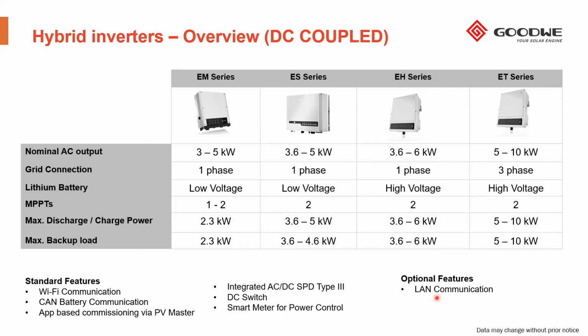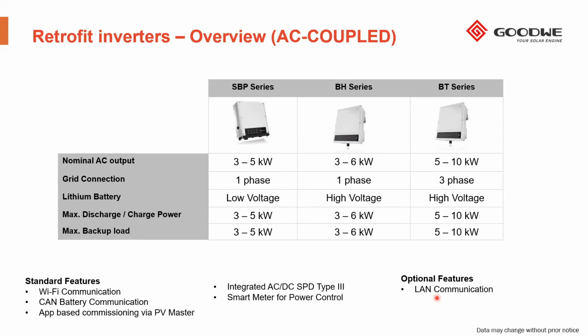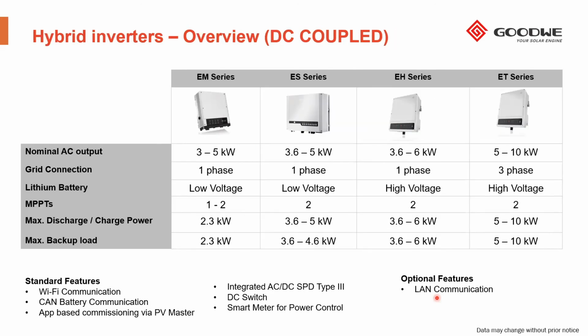There was also a question about backup load. It's actually the load that is connected on the backup output of the inverter. So if the AC side falls off, so it goes off, then the backup output will be activated, and energy is fed in through the battery to the backup load. Yes, that's right, and I'll take you through that in a couple of slides.